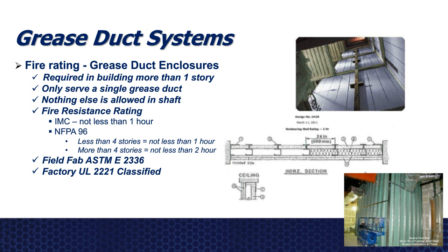Several years ago, code allowed either a field fabricated grease duct system that was designed and constructed per the engineering standard 2336 to be considered its own integral shaft and chase and not have to have a fire rated shaft to be routed in. Or a factory-built UL classified 2221 product could be utilized, allowing us to not have to use a shaft.